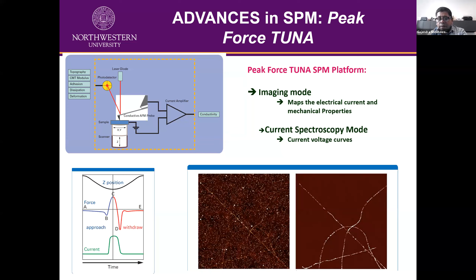So you can do a lot of these electrical measurements here. You can go from femtoamp to nanoamp to microamp. We have this capability in our system. All these Icon systems have the capability of doing peak force, so you can do both. You can map the electrical current, but you can also do the mechanical properties simultaneously. We also have a current spectroscopy mode, where you can do current-voltage characteristics, and it's pretty quantitative. Then we have a tapping mode AFM.